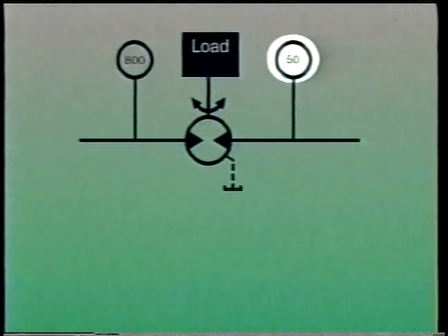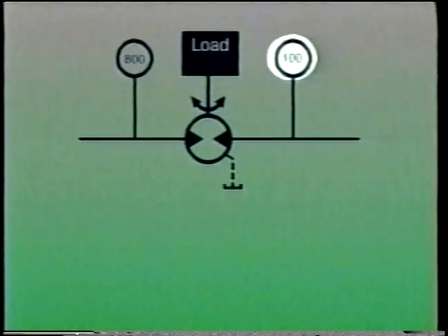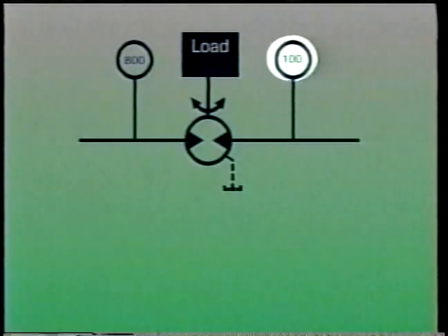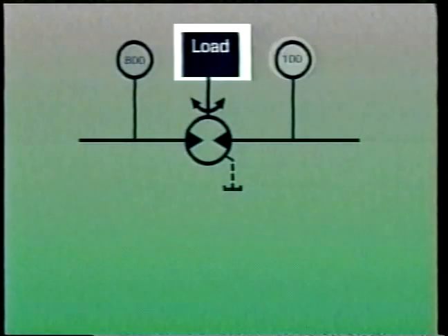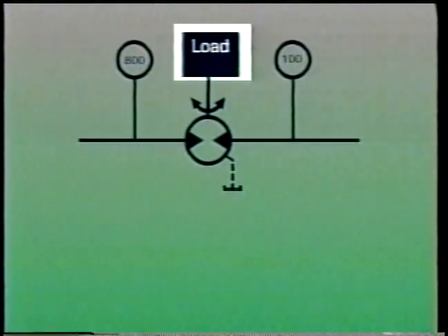Changes in outlet pressure occur in all industrial systems because there is always some back pressure present in the tank line. Usually, back pressure is at least 50 psi. And frequently, it's as much as 100 psi or more. In this system, 100 psi back pressure prevents the motor from moving the load because back pressure attempts to turn the motor in the opposite direction.